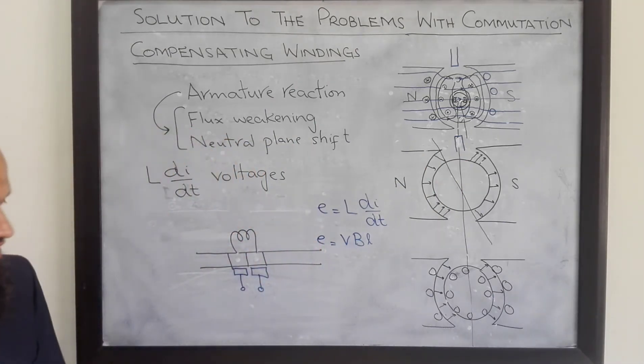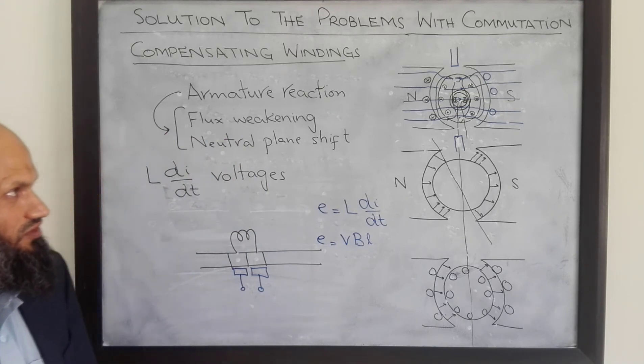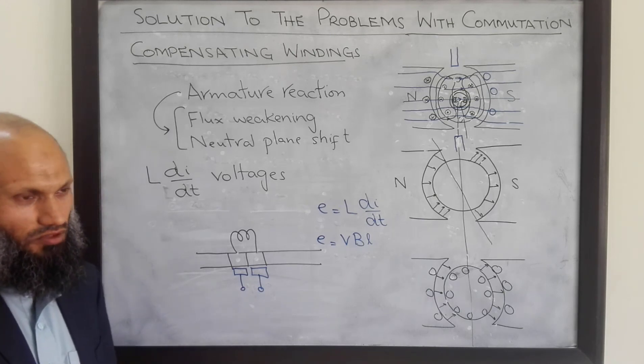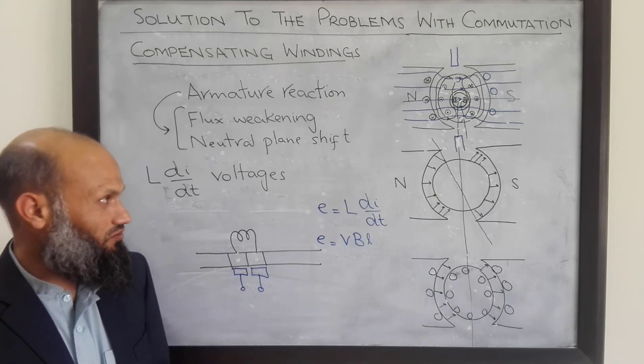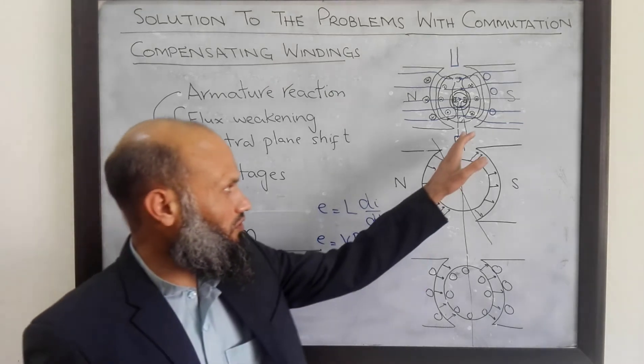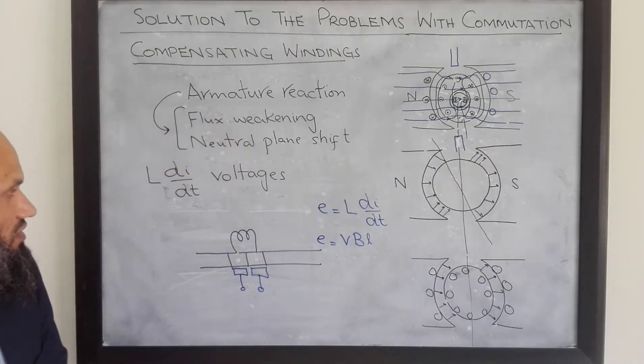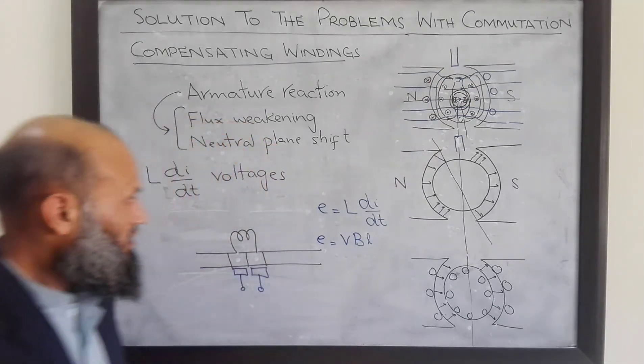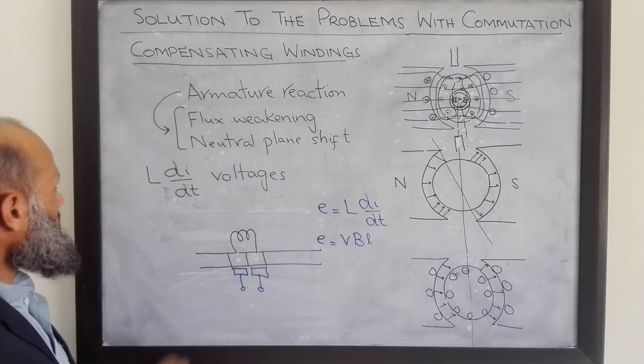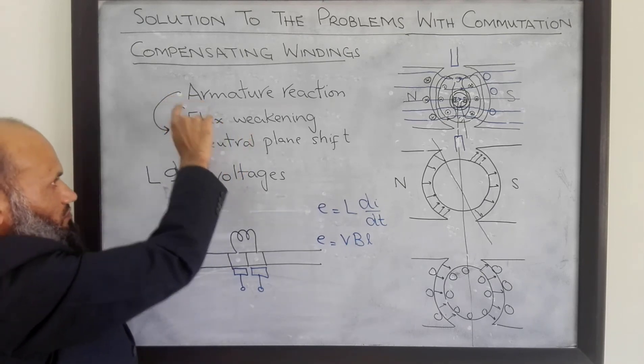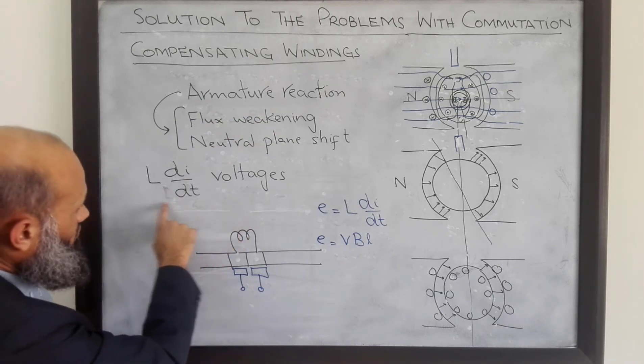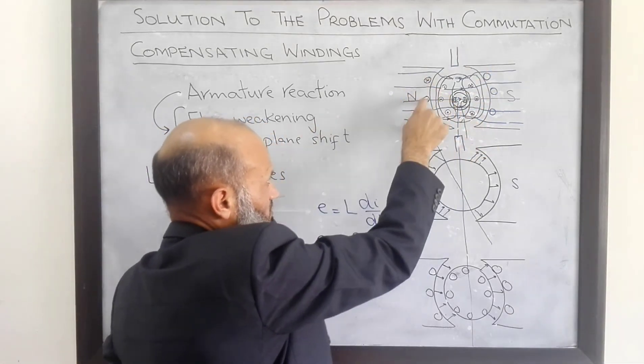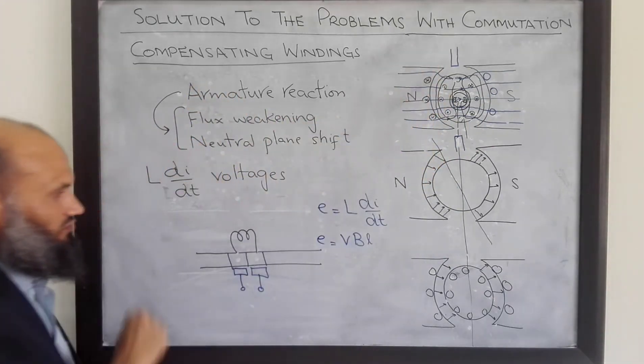In summary, we talked about three possible solutions. Brush shifting can to some extent resolve the problem of neutral plane shift, but cannot completely resolve it, and the flux weakening problem cannot be handled by this approach. Inter-poles resolve the problem of neutral plane shift and the L·dI/dt inductive kickback effect, but cannot resolve flux weakening. Compensating windings resolve the problem of neutral plane shift and also flux weakening; however, they cannot resolve the inductive kickback voltages. So in more expensive machines, they use both compensating windings and inter-poles — compensating windings to resolve the armature reaction effects and inter-poles to resolve the inductive kickback.